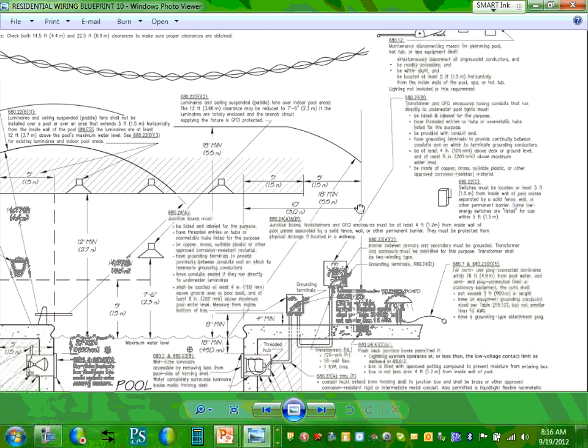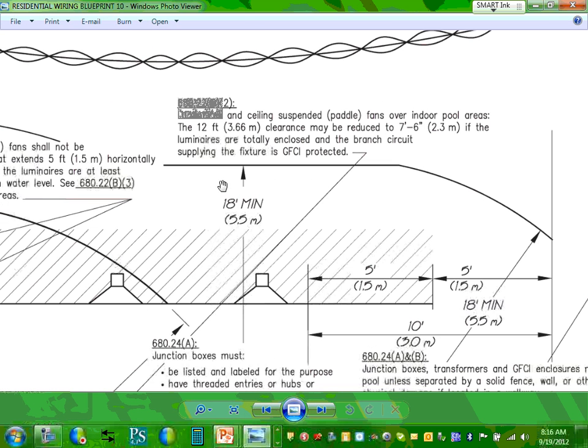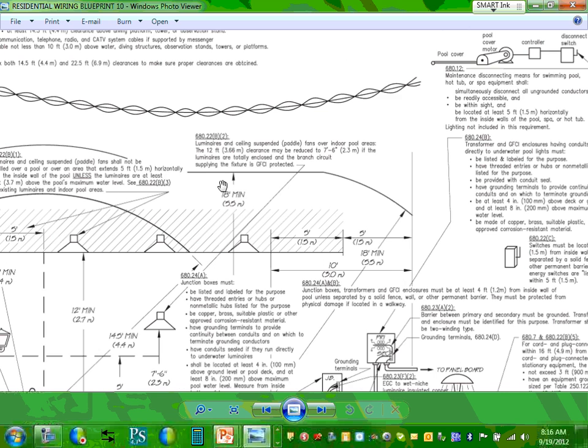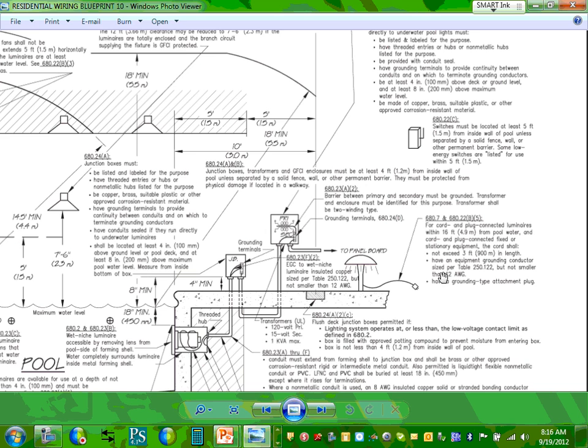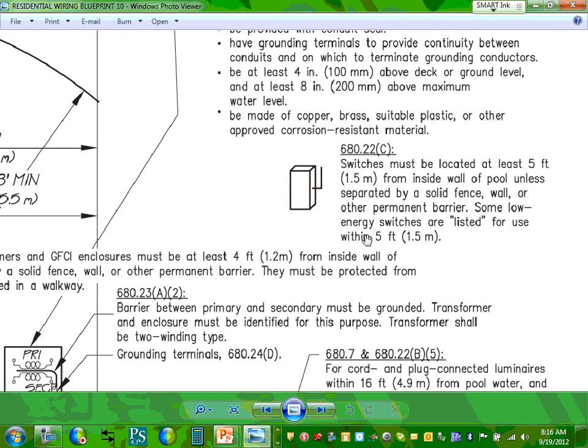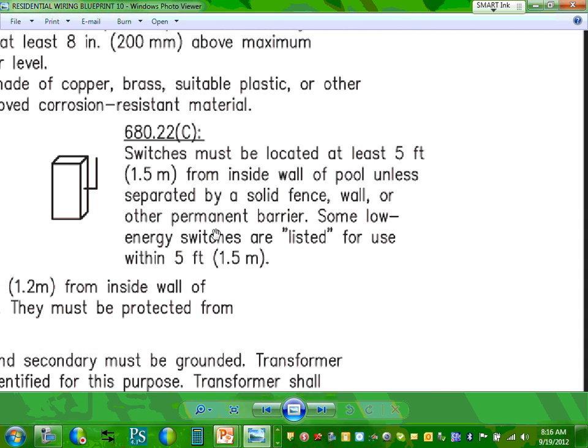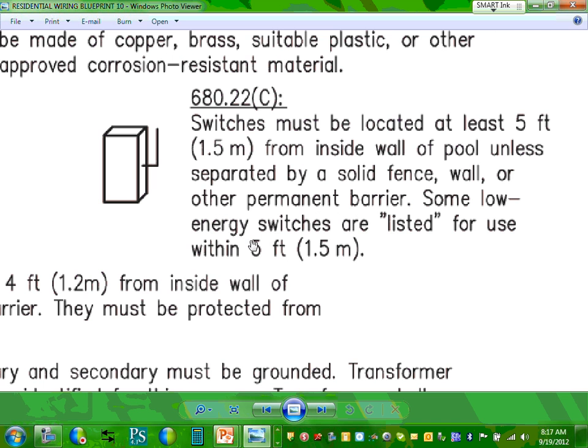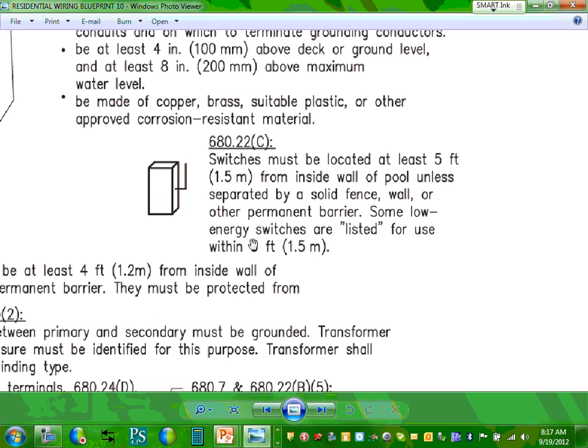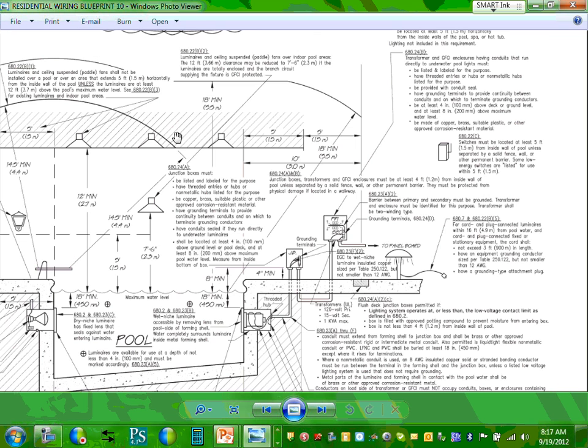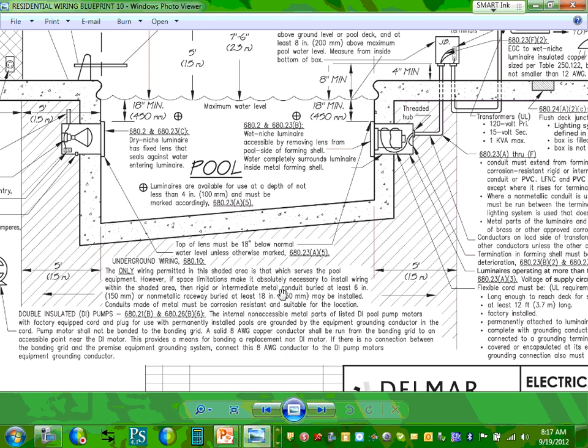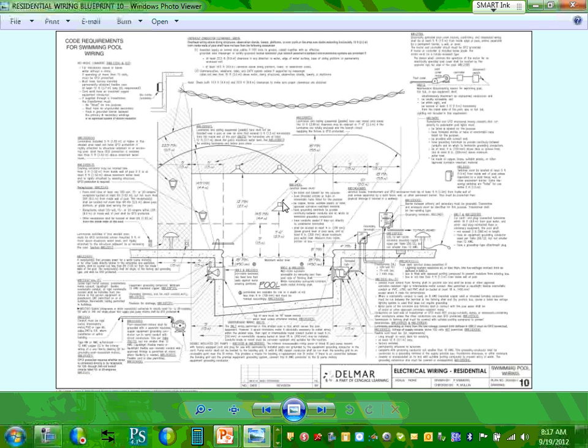Any comments, guys? Any questions about these? And I'm picking and choosing certain things here. Okay, cord and plug, switches. This is interesting. Switches. How about switch for light? Look at that. Switches must be located at least how far? 5 feet from the inside wall of the swimming pool. Low voltage switches are listed for use within the 5 feet. Now we have a low voltage switch. You can put it within the 5 feet. High voltage switches, 5 feet. Any comments? Any questions, guys, about that? So this will summarize basically the whole requirement for you.